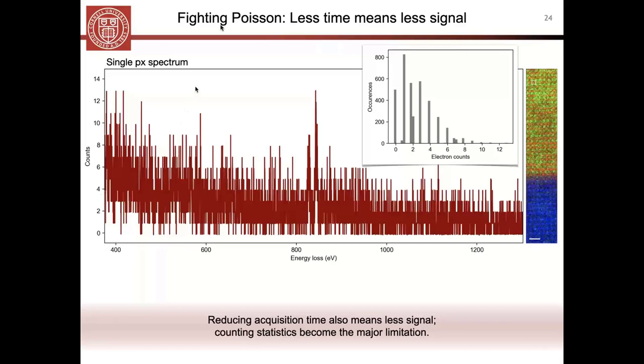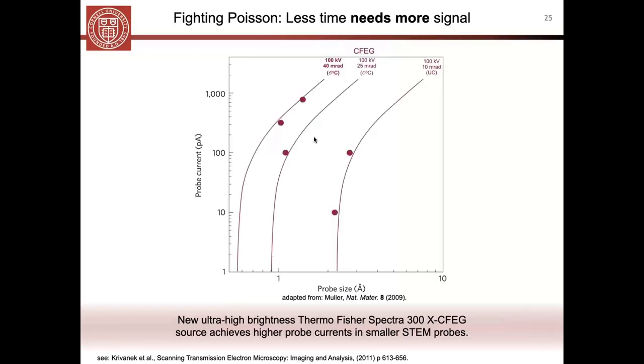So really what this means is, having outrun the drift of the holders by moving to these fast, low noise detectors, what we're really up against now is just the statistics of the experiment. So to increase the signal without increasing the time, the way you can do that is by actually increasing the number of electrons that you put through your sample.